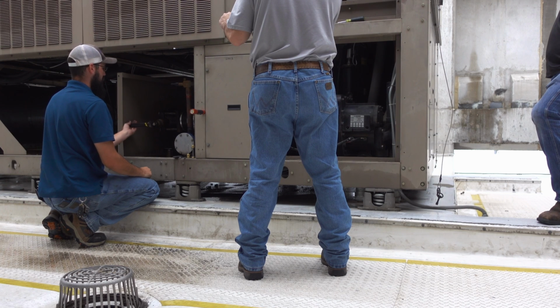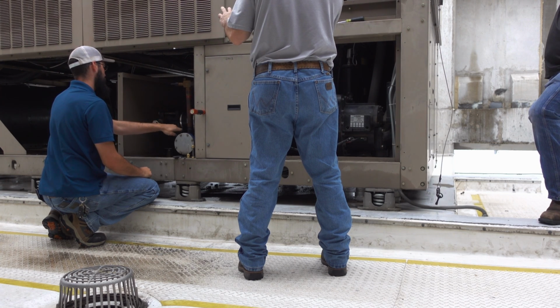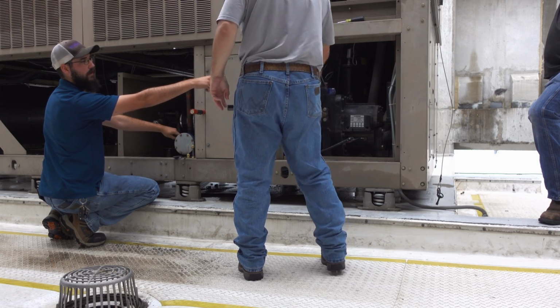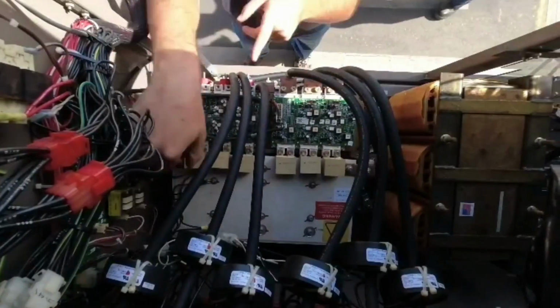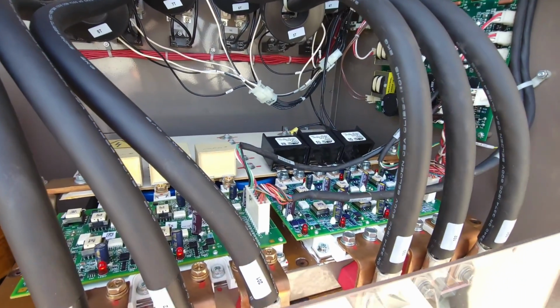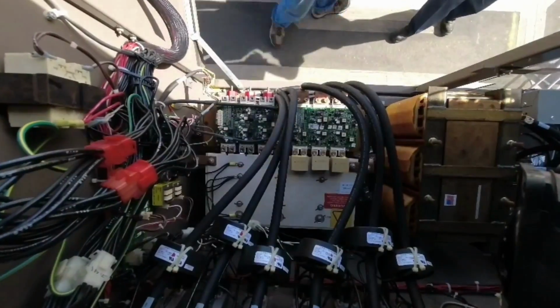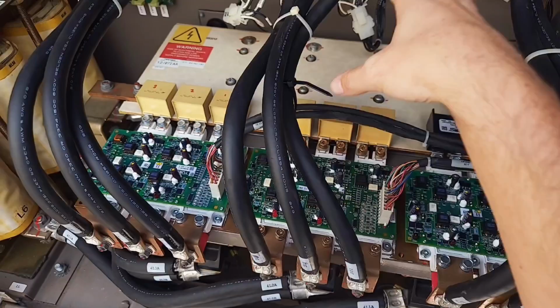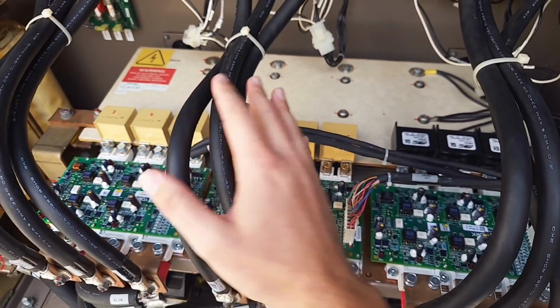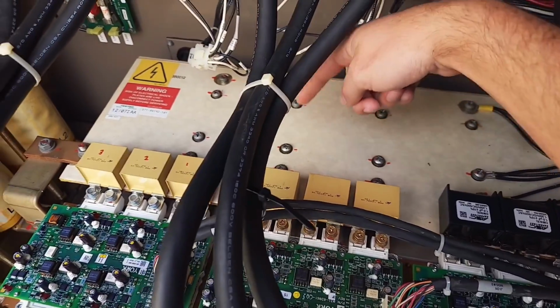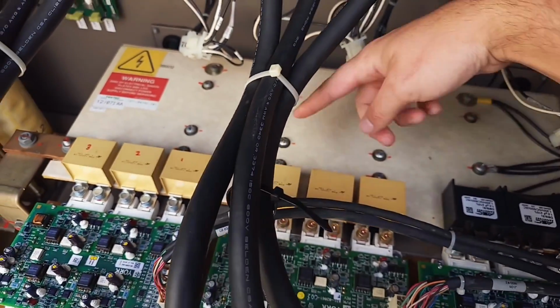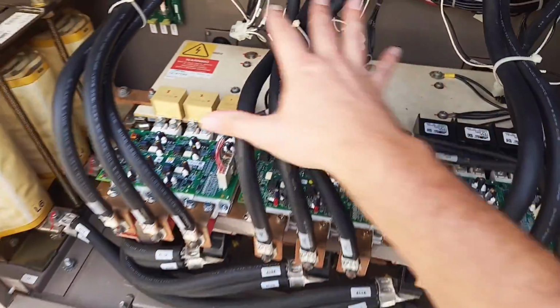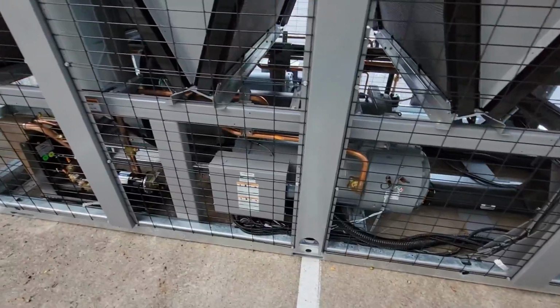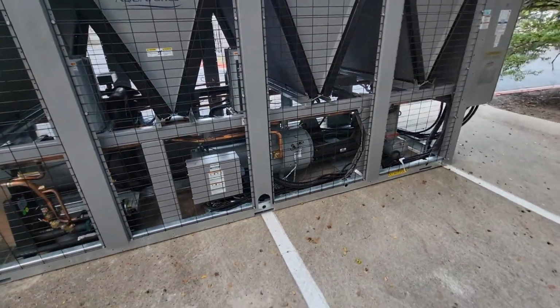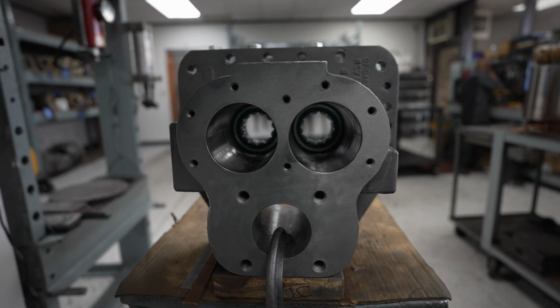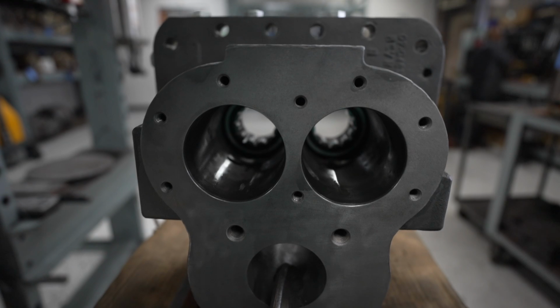Now, the second style, and it's going to be the more common thing moving forward, is variable speed. Instead of having a slide, we'll have a variable speed drive run that compressor up and down in order to just increase the physical RPM. By increasing or decreasing the RPM, the speed that the motor is spinning at, we're able to change how much refrigerant flows through it that way. Now, we still have the RLA limitations and trying to meet our leaving water set point, so those two things still have to balance just the same. It may be a 60 hertz motor. We may be at RLA at, say, 40-50 hertz depending on our load conditions, and we may not be able to run at that 60 hertz and still safely control the motor. So these are things we have to balance still. That's not removed from the equation.